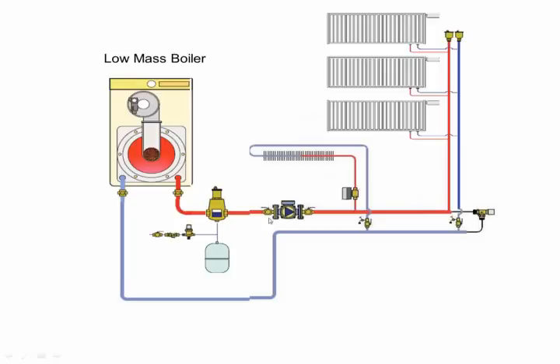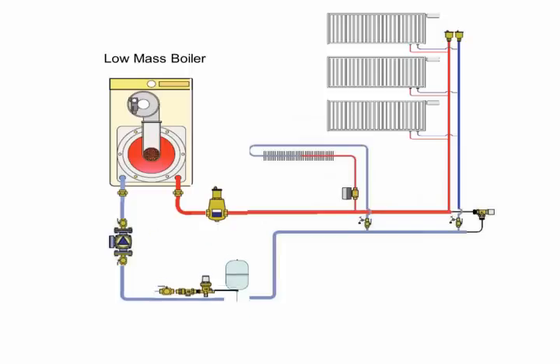In a low-mass condensing boiler, in many cases, the manufacturers want to maximize the pressure in that boiler. So rather than pump away, they want you to pump into the boiler, because that does what? It raises the temperature at which you can get flashing. And flashing creates what? It causes stress in your heat exchanger, and it should basically reduce the life expectancy of that heat exchanger. So pump into these types of boilers, okay? But now we're pumping into the expansion tank, so make sure you pump away from the expansion tank.